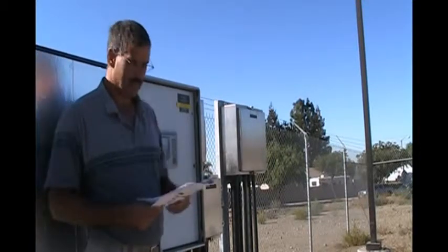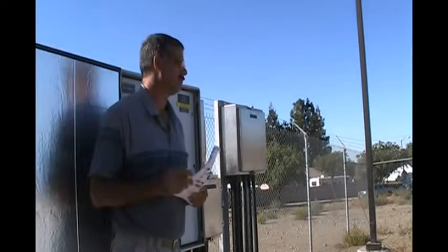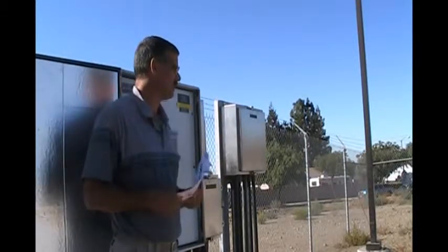Okay. And then you also see over on the right, you'll have the status of I/O. This also gives you a little bit of a troubleshooting indication. If you're having trouble out here, you know the valve's closed, but you're not getting that signal. This is confirmation that you need to go ahead and do some sort of repair work on the valve close signal or the valve open signal, and so on.